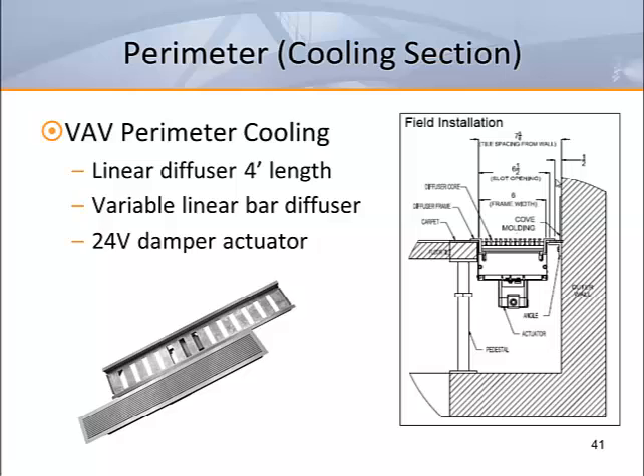The unit shown in the lower left-hand corner of the slide is a 4-foot-long VAV cooling supply air unit. The installation view shows the simplicity of the installation on the perimeter for this product. The product is flanged on both sides and rests on top of an angle iron on the exterior wall side. This angle iron is field installed and supplied by others. The exterior wall side flange of the grill simply rests on top of the carpet tile and then on the angle iron. On the room side, the inside flange of the product rests on top of the carpet tile as well. There are no tools required to install this product, which makes it very easy to access if needed. Once the unit is installed, the continuous length of linear bar grill mounts on top to complete the installation.